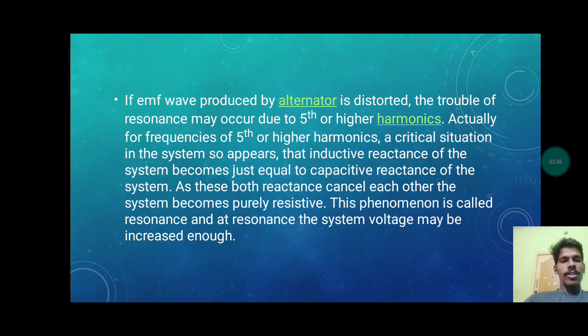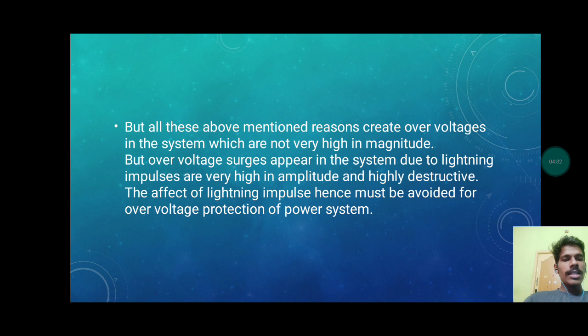If the EMF, electromotive force wave, produced by an alternator is distorted, the trouble of resonance may occur due to fifth or higher harmonics. Actually, the frequency of the fifth or higher harmonics is a critical situation in the systems. It appears that the inductive reactance of the system becomes just equal to the capacitive reactance of the system. As these two reactances cancel each other, the system becomes purely resistive. This phenomenon is called resonance, and in resonance the system voltage may be increased enough.